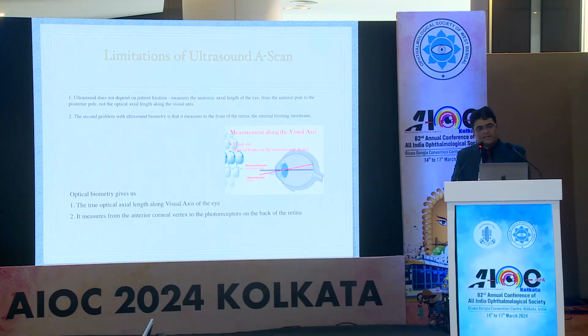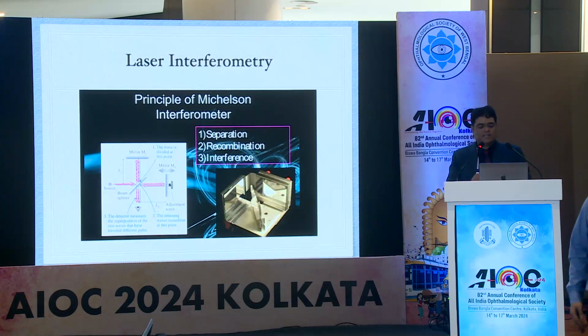So these are two differences where optical biometer, we all know, scores over ultrasound A-scan, and why we should all shift to optical biometers. Then secondly, we all know that if you are using ultrasound, of course you have to go for immersion biometry. Contact is of course a big no, because indentation always comes in when we are doing applanation biometry.